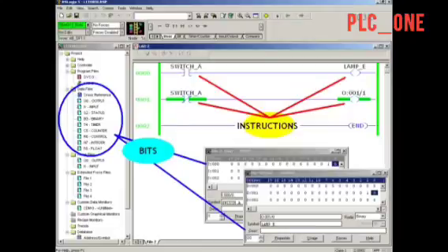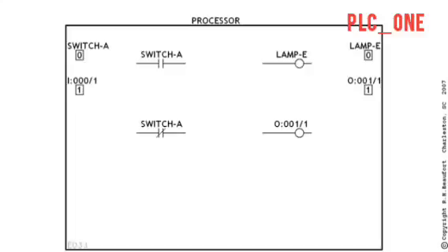And here's what they'll look like in the RSLogix software. Instructions live in the ladder program, and you can access the bits by opening up the data files. Many of your hands-on troubleshooting exercises in the boot camp will involve forcing inputs and outputs and toggling bits, and understanding the effects those operations have on various instructions in the ladder program. Now let's go back to our sketch and add another bit or two. Here's a bit, a box, with the address B3/0, and one more, T4:0/DN, and this is where we'll leave our setup, for now at least.